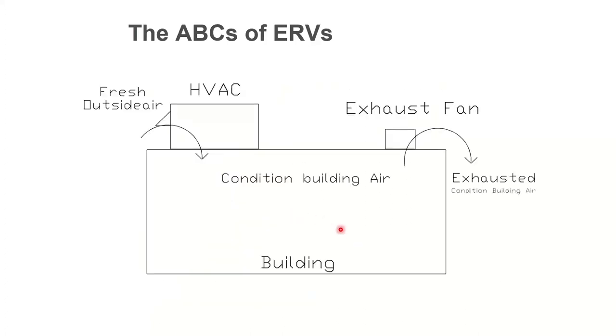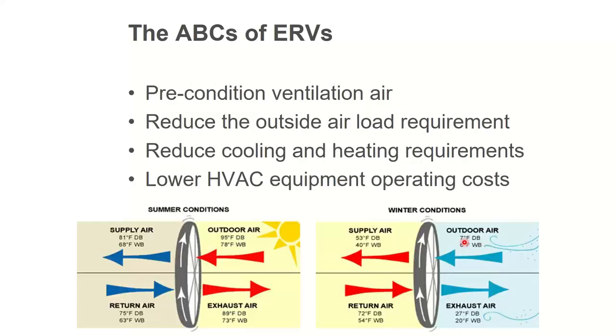I also need to get the airstreams close to each other. In this example over here, there's a rooftop with an outside air intake on one side of the building. The other side of the building has an exhaust fan exhausting out. That's going to be a difficult one to do an ERV on. I need those things close to each other, right next to each other, preferably, and that makes it significantly easier to do.